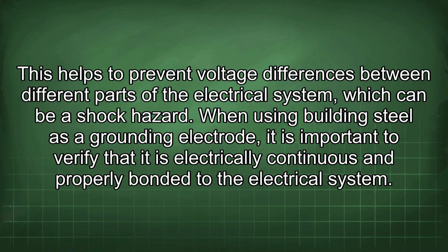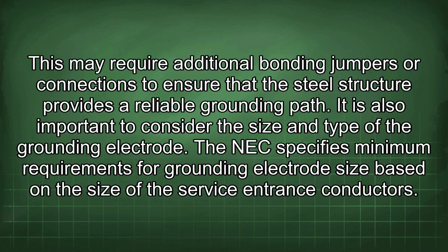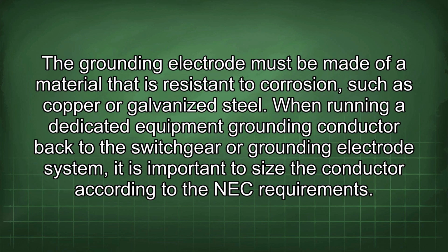When using building steel as a grounding electrode, it is important to verify that it is electrically continuous and properly bonded to the electrical system. This may require additional bonding jumpers or connections to ensure that the steel structure provides a reliable grounding path. It is also important to consider the size and type of the grounding electrode. The NEC specifies minimum requirements for grounding electrode size based on the size of the service entrance conductors. The grounding electrode must be made of a material that is resistant to corrosion, such as copper or galvanized steel.